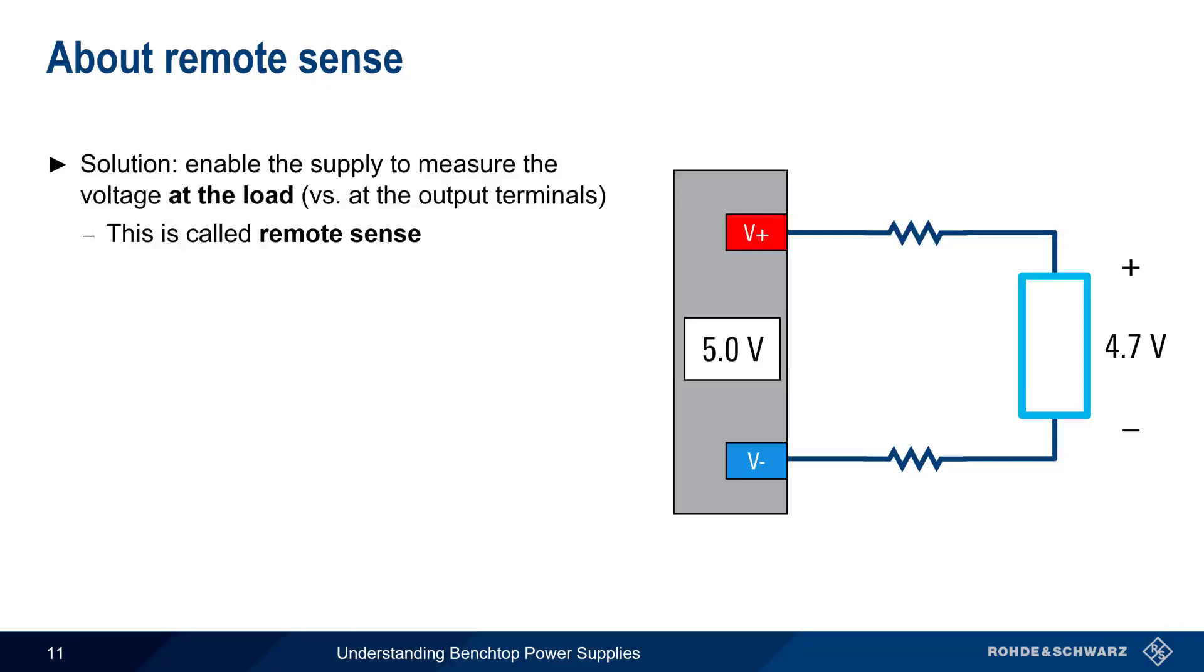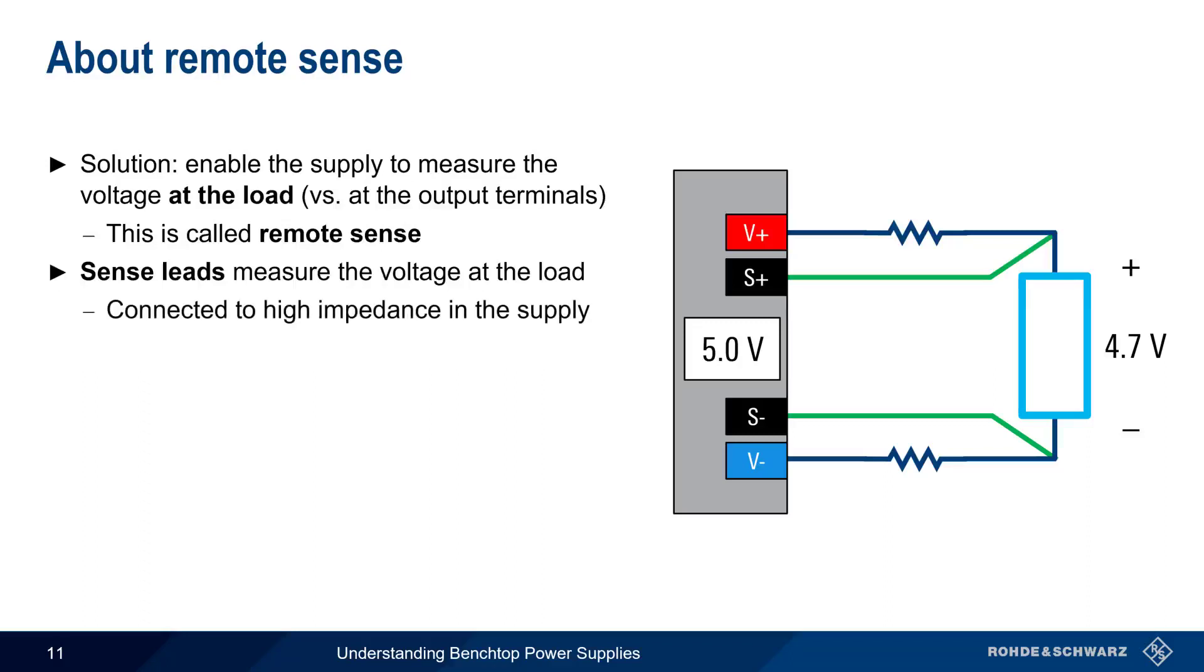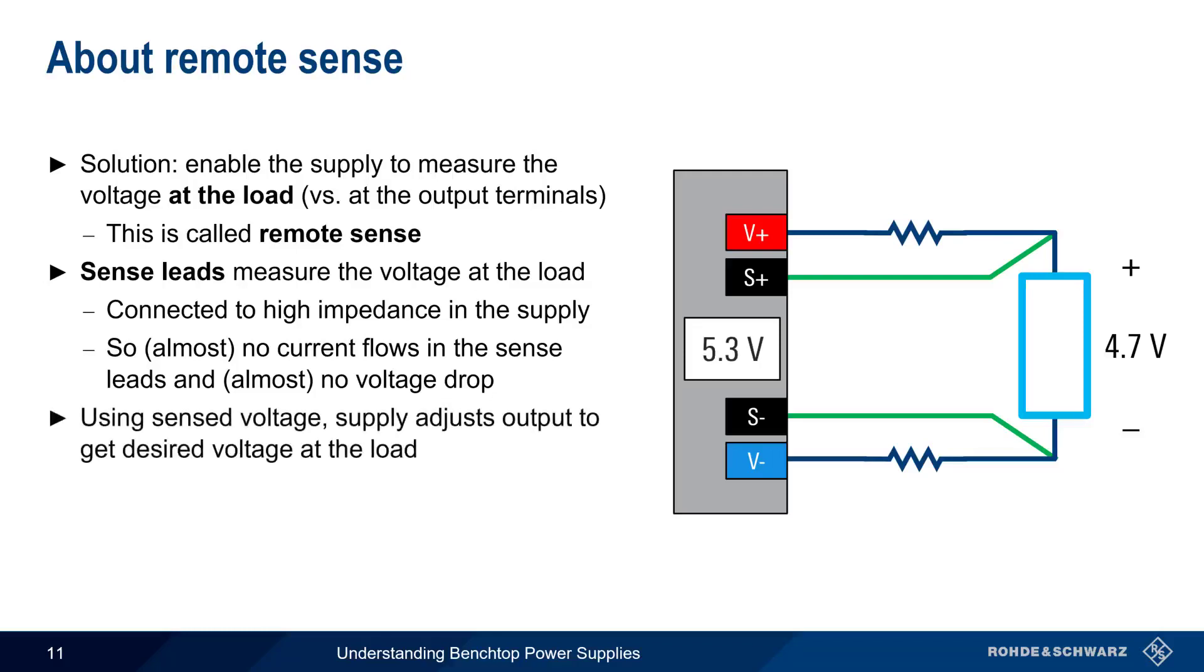In remote sense, an additional set of so-called sense leads are used to measure the voltage as close as possible to the load. These leads are connected to a very high impedance in the supply, meaning that almost no current flows, and therefore there is almost no voltage drop in these sense leads. Using the remotely sensed voltage, the supply can then adjust its output to obtain the desired voltage at the load. Here, the supply compensated for the 0.3 volt drop by increasing output voltage to 5.3 volts. Note that this is an automatic, dynamic process. Once the sense leads have been connected and remote sense has been enabled, the power supply will automatically and continuously adjust the output voltage as needed.